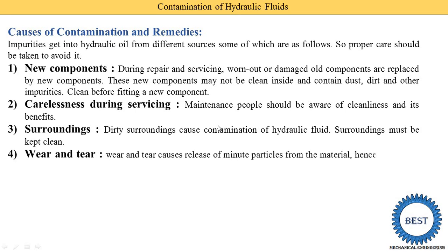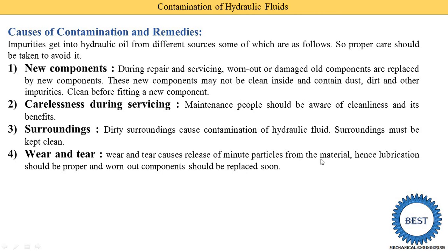The next cause is wear and tear. Wear and tear causes the release of minute particles from materials — these are called burrs — which are added into the hydraulic oil and cause contamination. To prevent this, lubrication must be proper and worn out components must be replaced promptly with new components.